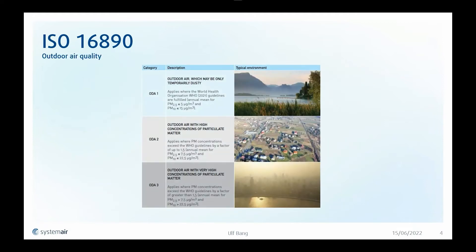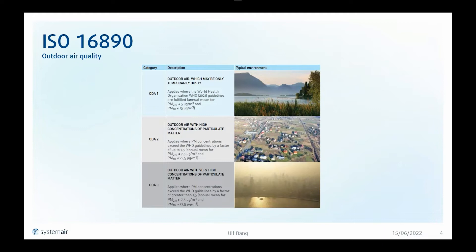The standard can also recommend what total filter efficiency you need for your system depending on the outdoor environment and the application. In this table, it classifies the outdoor environment in three classes: ODA 1, ODA 2, and ODA 3. ODA 1 is countryside and ODA 3 is mid-city.